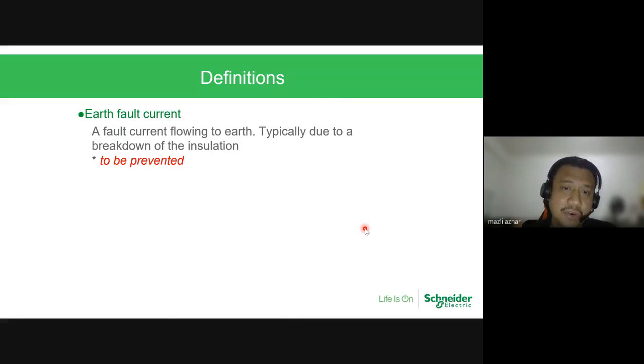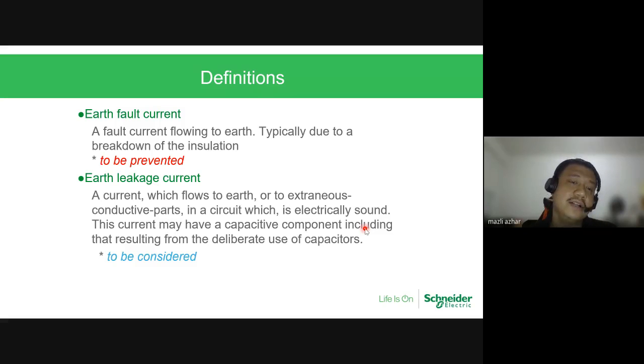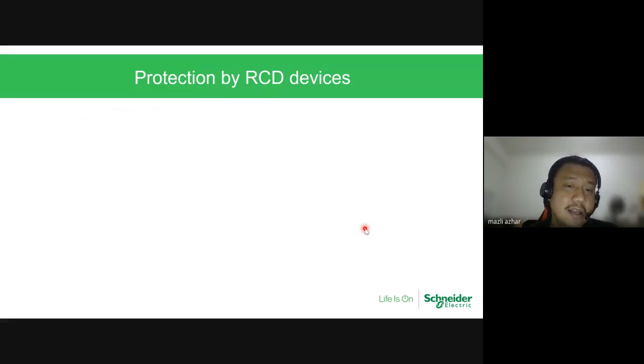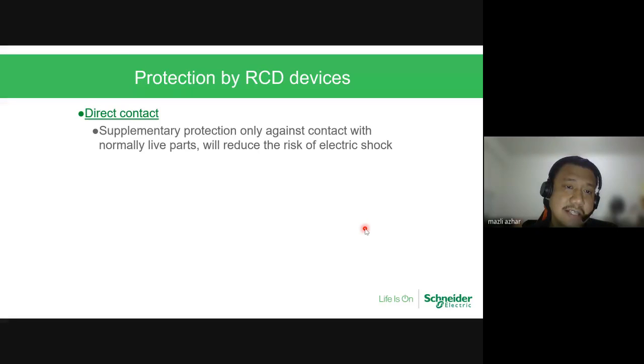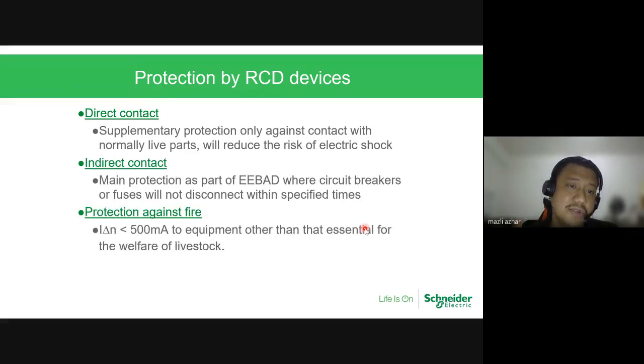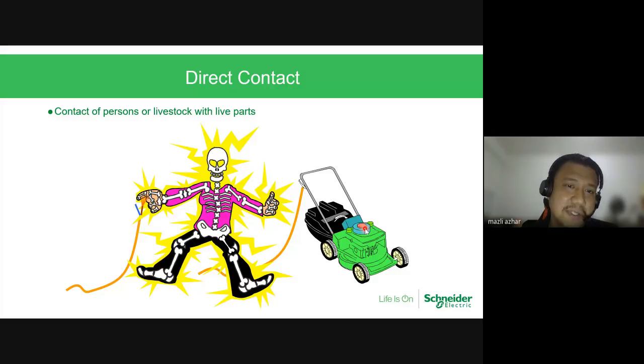So by definition of fault current, this is where the MCB comes into play. Earth leakage current is a current that flows to extraneous conductive parts. Okay. So protection by an RCD device can be by three components, which is for direct contact, indirect contact, or protection against fire. So for direct contact, it's very simple. A contact of a person or livestock with the live parts. When you see an open cable, you accidentally touch it, then we call it a direct contact. Then you get direct electrocution.